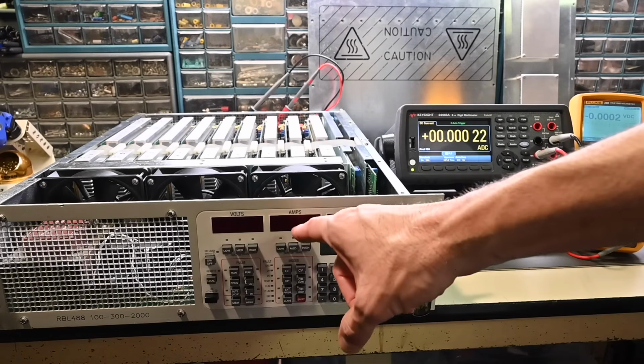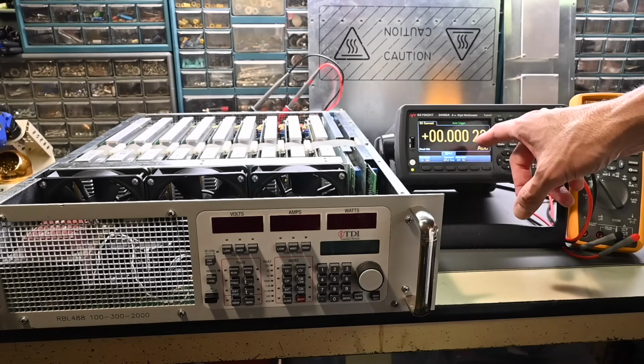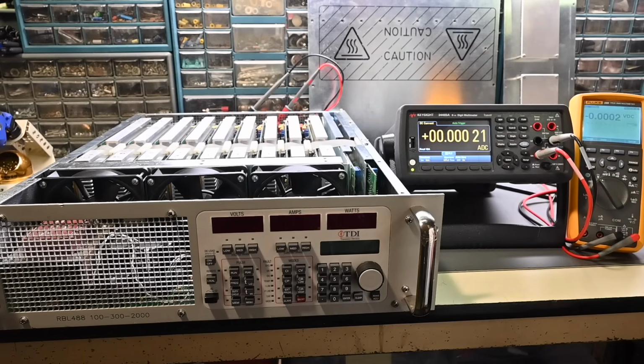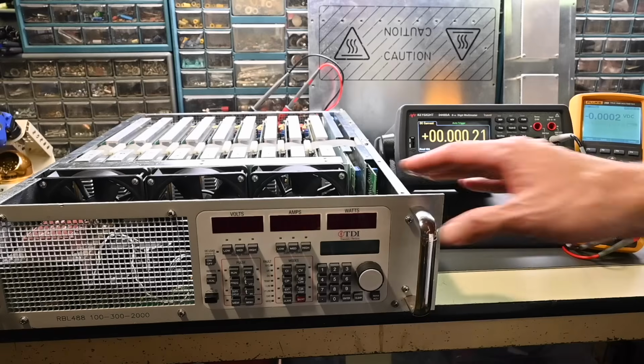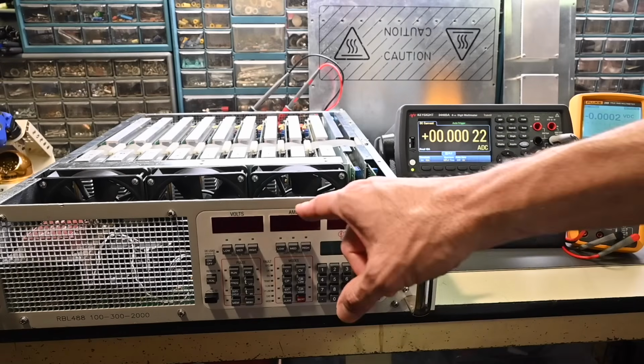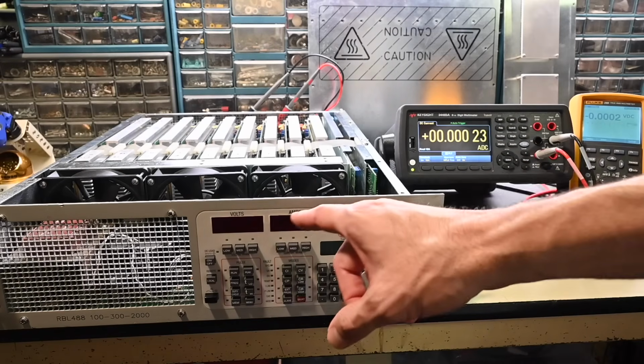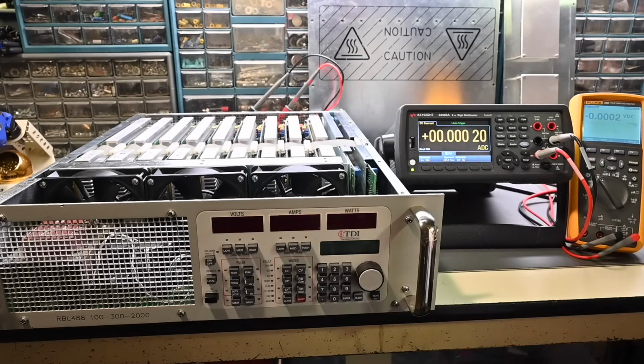And then this amperage reading right here should be the same as the amperage or current reading over here on the Keysight 34465A digital multimeter. So this is in series between the power supply and this electronic load. So again, we're watching for this to match right here. And of course, the product of voltage and amperage is the wattage. So just multiplying those numbers together should give us the reading that we see there. All right, so here we go. Let's see what happens.